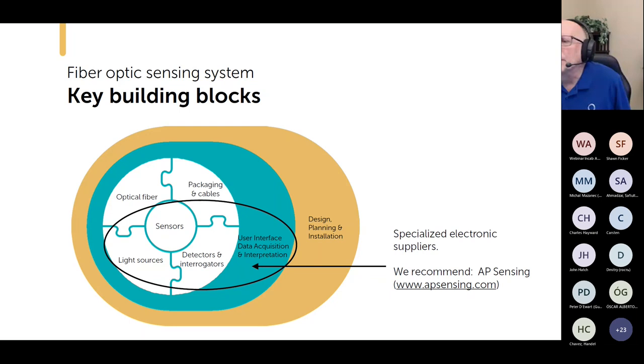Can an empty blown fiber duct be pulled in along with an underground cable? Yeah, that's a possibility. Are sensor electronics commercially available for lightning and temperature sensing in underground cables? For the temperature sensing for underground cables, absolutely. That's been done for at least 10 years now that I know of. For lightning, that's newer. We did some testing, so we know it can be done, but I don't know of any utility who's actually put it into practice yet.